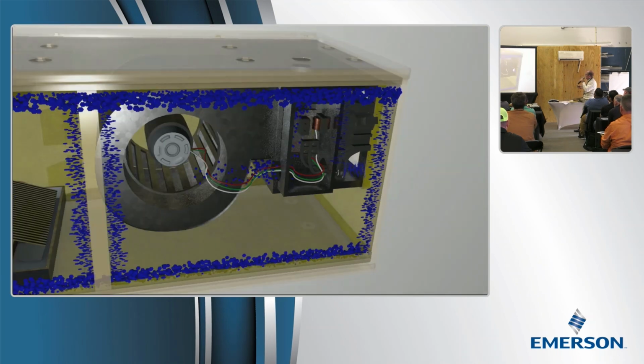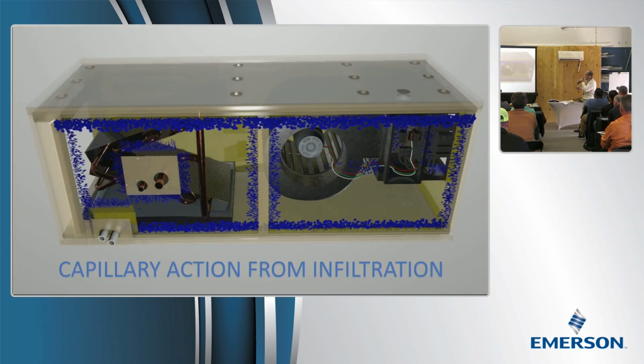But here's the big one, just the cabinet leakage. You've all seen that. That's where it leaks. It's just nobody does anything about it until you pressurize it. When you pressurize the cabinet, everybody gets excited and starts sealing it. Oh, there's air coming out. But as long as you can't see it, right, it's sucking air like crazy. You can see it with smoke. Give it a little smoke and you'll see this going on.